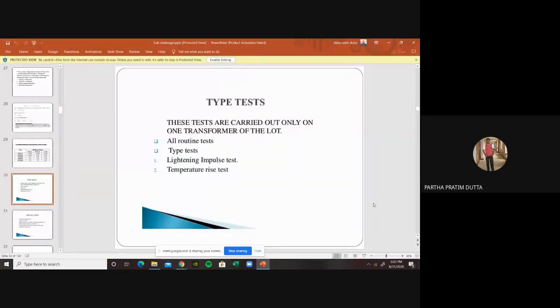Now I will talk about the type test. These tests are carried out only on 1 transformer of the lot. Lot means maybe I am procuring 100 transformers. In that case, I choose 1 transformer randomly and do this test. If the test results are okay as per the specification or IS standard, we can consider that this particular lot of transformers is okay. That is why it is called a type test.